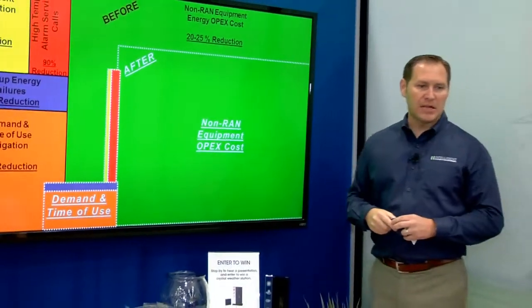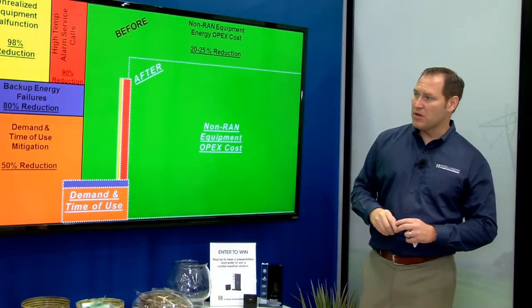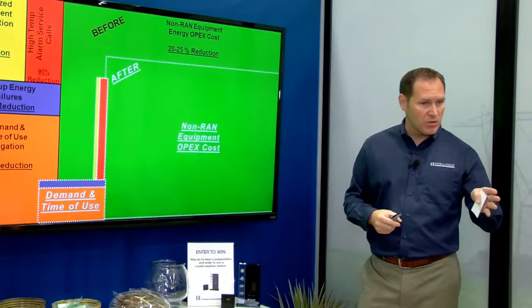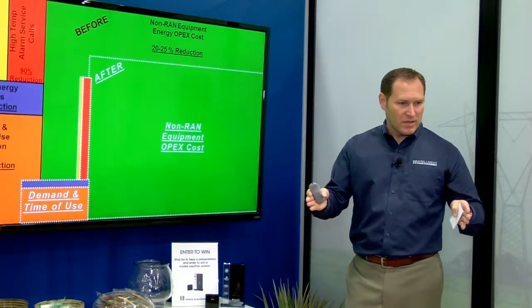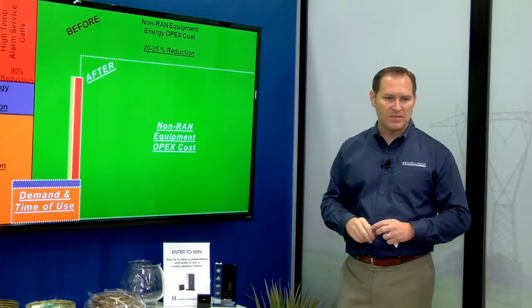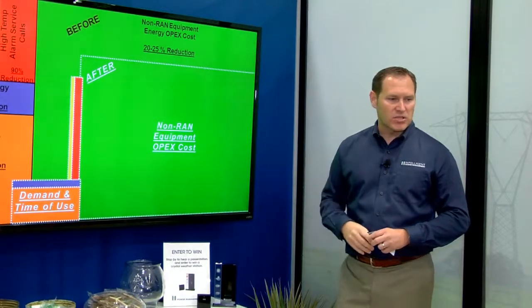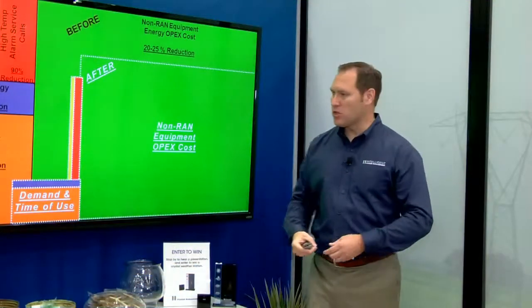We've reduced unrealized equipment malfunction and energy waste by 98%. High temperature alarm service calls — more often than not, high-temp alarms are false alarms — we've reduced those by 90%. For backup energy failures, we found one particular customer where we went out in January, went out again in September, and the generator hadn't started once — the fuel reading was still the same on the gas meter. So we can proactively start and stop generators, or tell customers at an enterprise level when the last maintenance was performed and whether it improved generator efficiency.